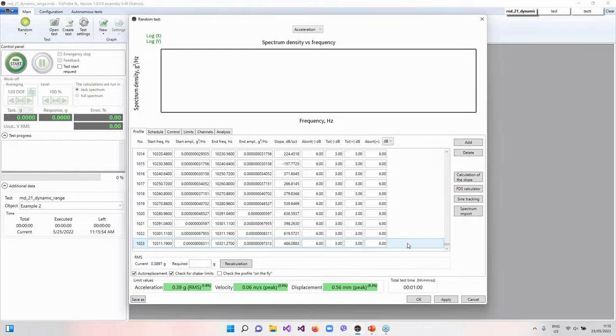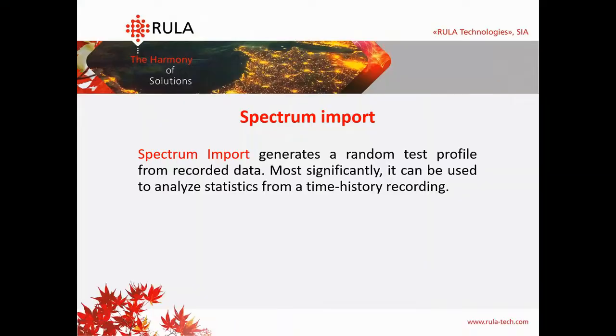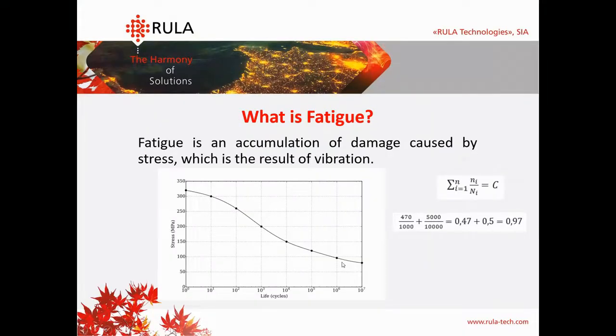To compare the results, let's continue with the fatigue damage spectrum test. Going back to our presentation. Our first step is to talk about fatigue. Fatigue is accumulation of damage caused by stress, which is the result of vibration. Here you can see the graph which represents a stress-to-cycles curve. All the calculations of fatigue are made with the Palmgren-Miner rule.